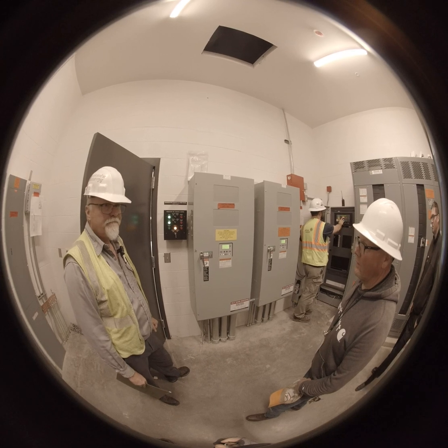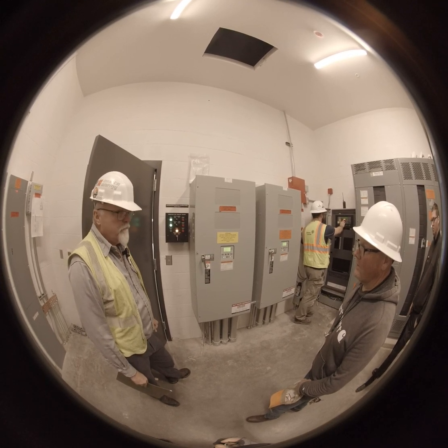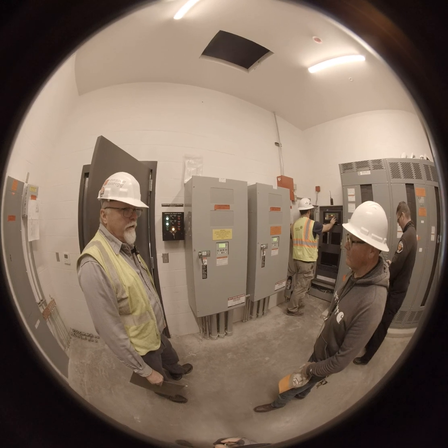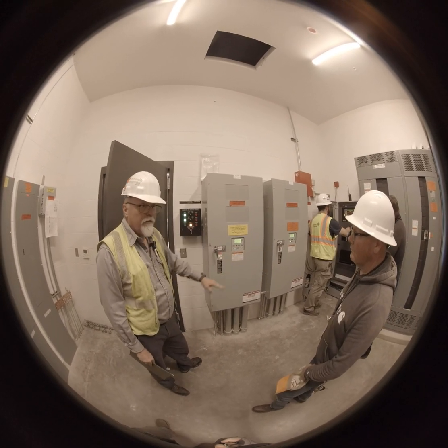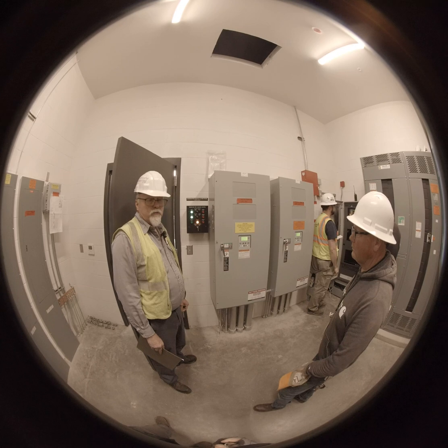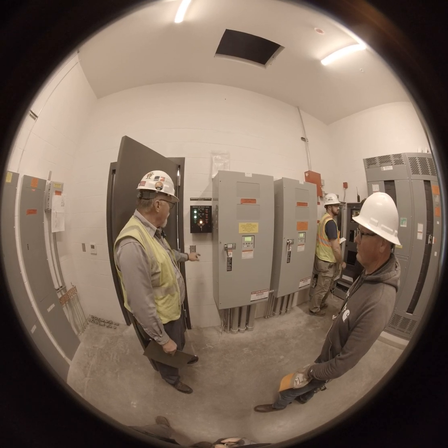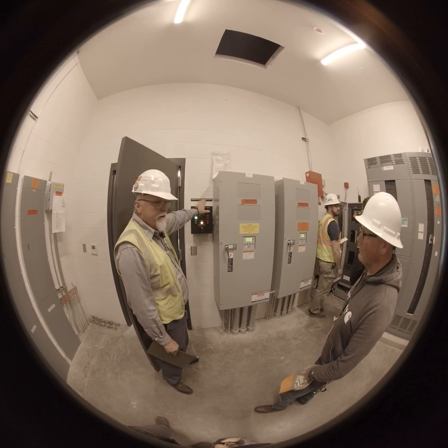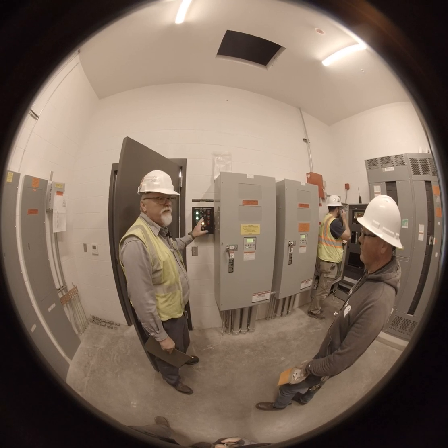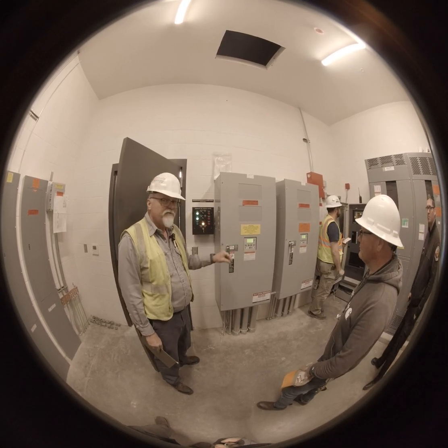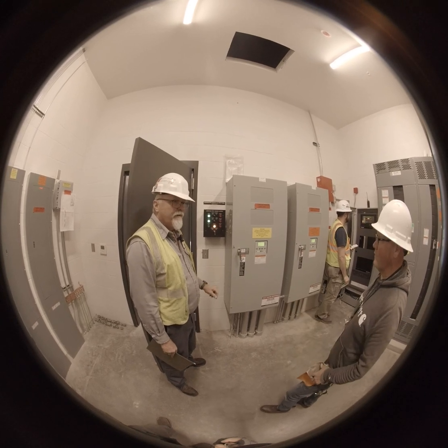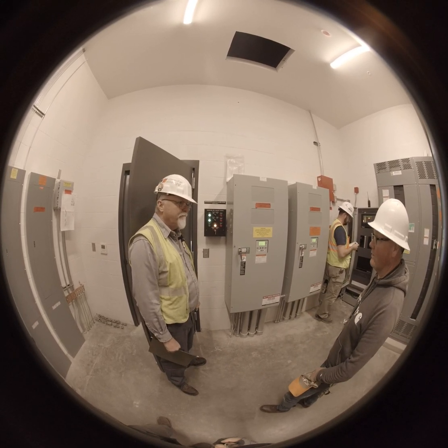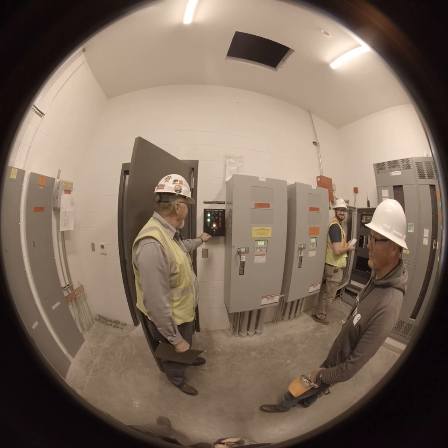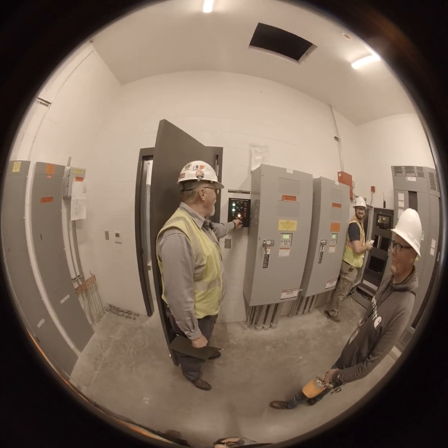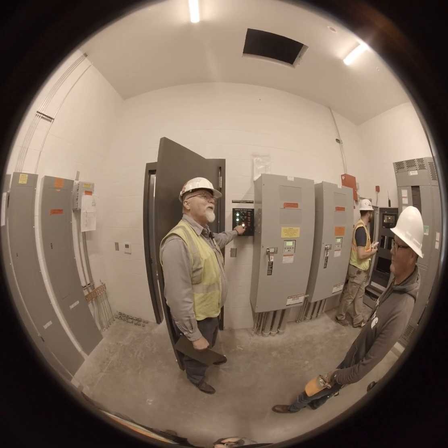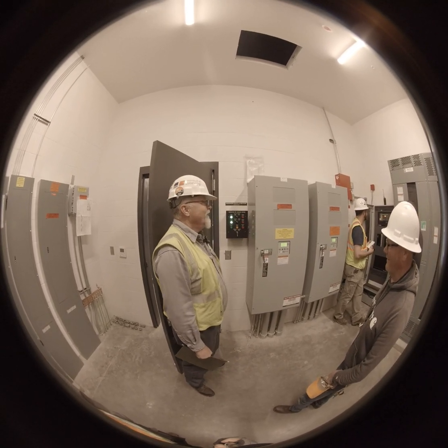Will that be shown on the annunciator and sending an alarm or anything? No. The annunciator does not monitor the transfer switch. Even though you're out of auto here? We're not out of auto. We're still in automatic at the machine. We close that remote set of contacts, the same as what's in these transfer switches. This is the first generator I've got that's got this capability. Nice. Just like your supervisor too, that the engine's running? Oh, cool. Well, you're welcome. It should have cleared.